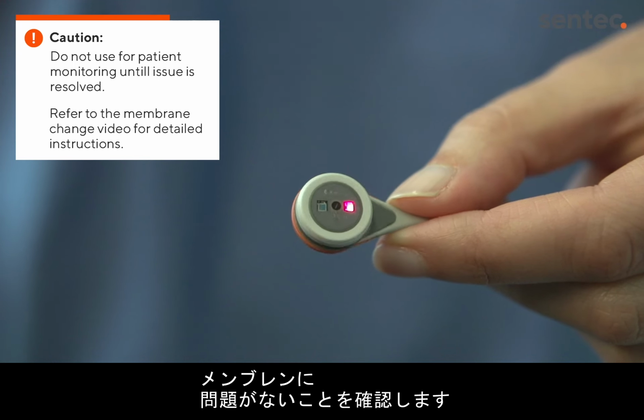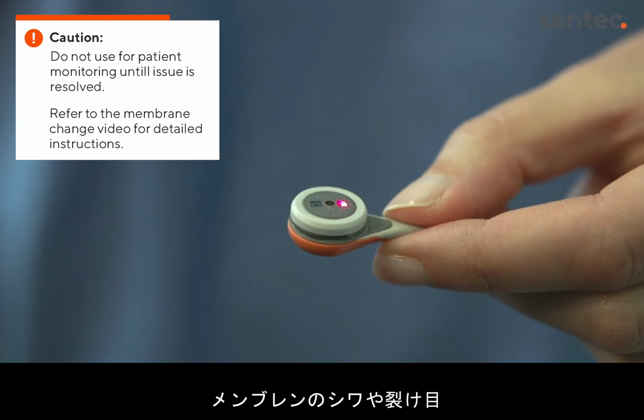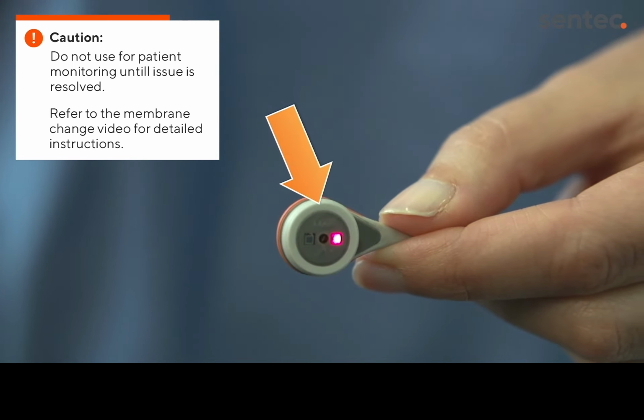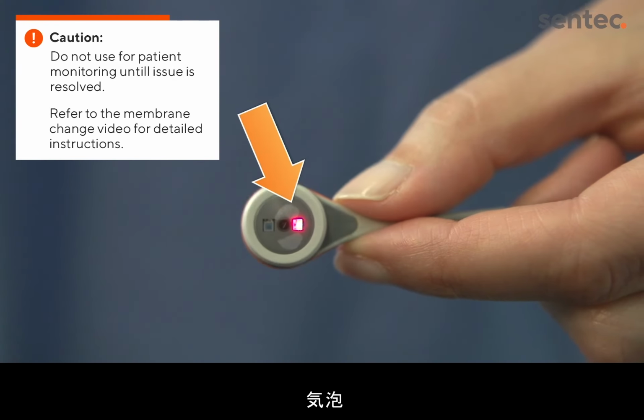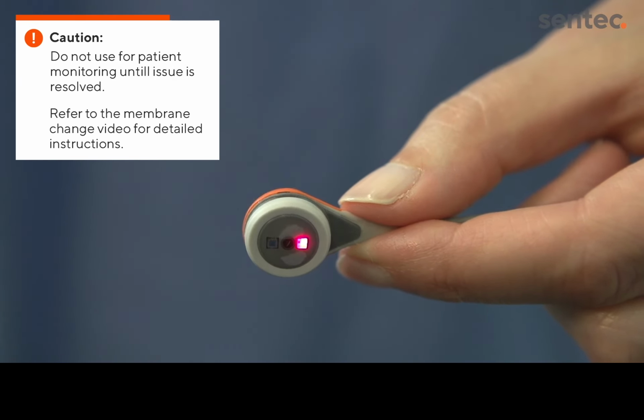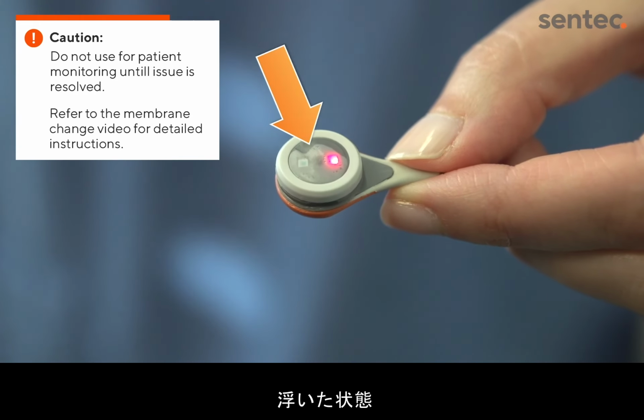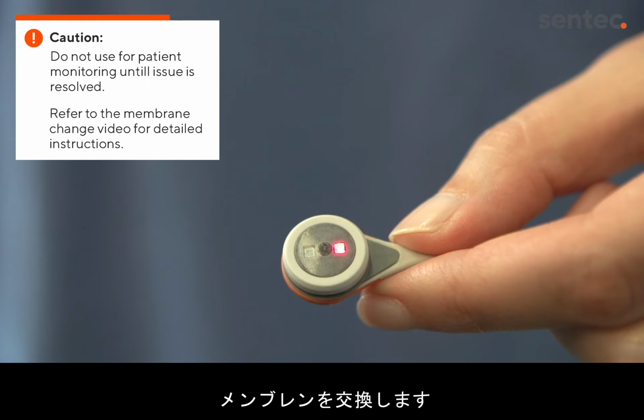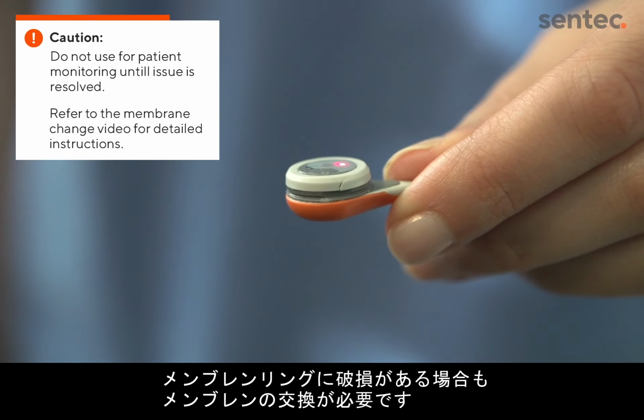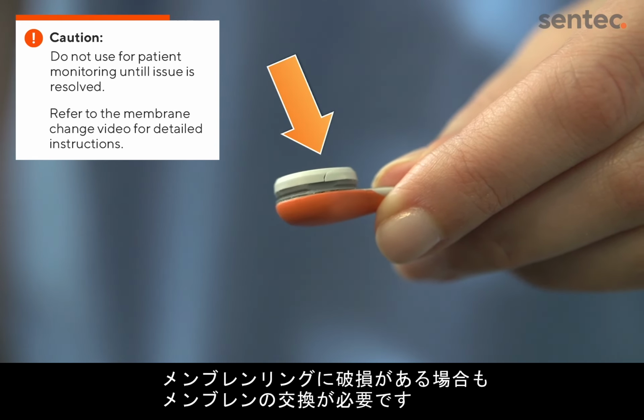Next, check the integrity of the membrane. If the membrane is wrinkled or torn, there are air bubbles present, the membrane has a loose fit, or the electrolyte is dried out, the membrane needs to be changed. The membrane must also be changed if there is any damage to the membrane ring.